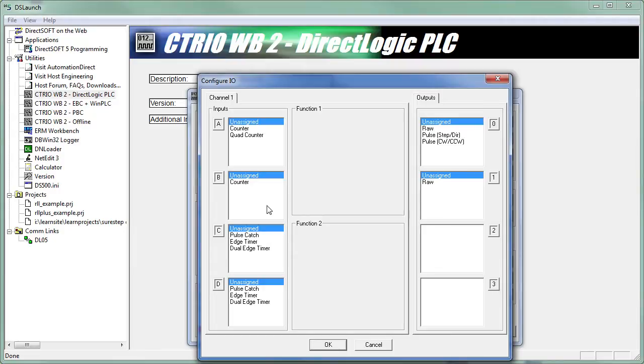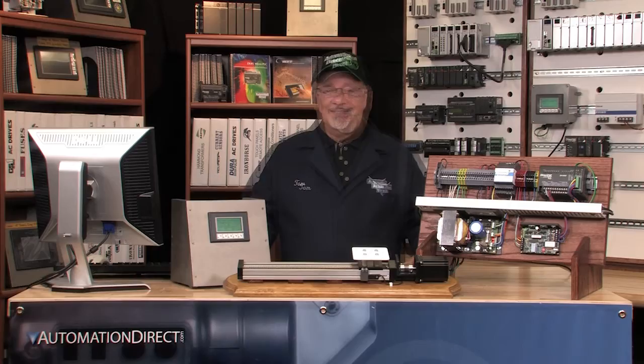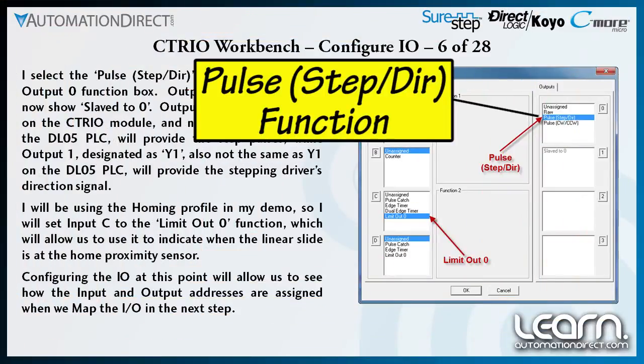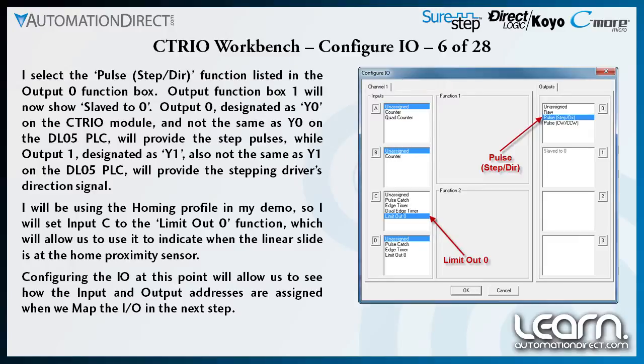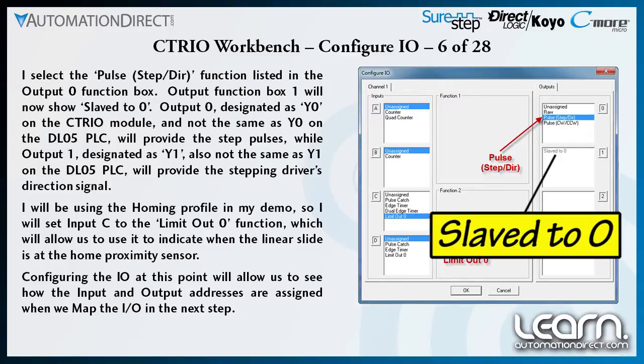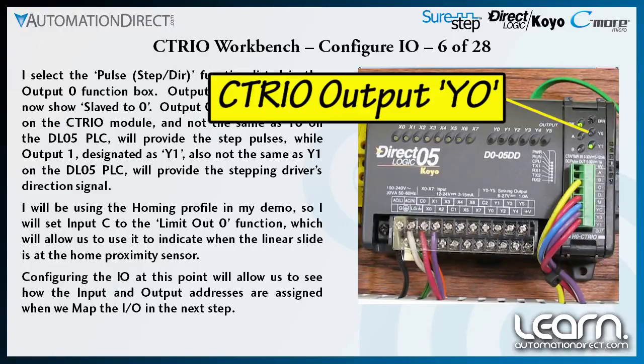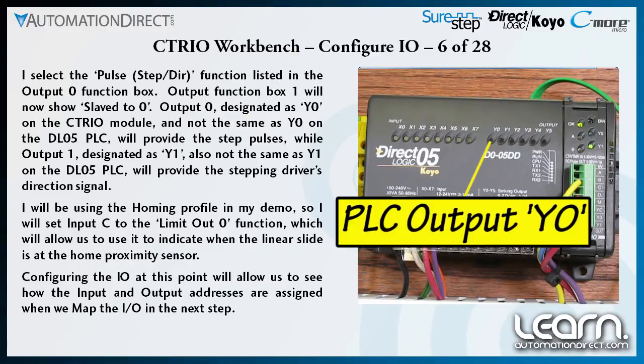The various functions within each input and output function box can change based on the selections made in some of the other function boxes. For my application, I select the Pulse Step Direction function listed in the Output 0 function box. Output function box 1 will now show slave to 0. Output 0, designated as Y0 on the CTRIO module — and not the same as Y0 on the DL05 PLC — will provide the step pulses.